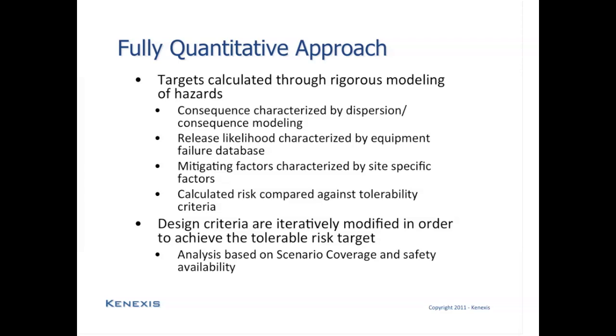The release likelihood is going to be calculated, but it's going to be calculated in a way that is drastically different than many people would expect, especially if they have a background in doing the simplified layer of protection analysis technique. With a fire and gas detection and suppression system, we do not assume that we are going to be able to know what the causes of loss of containment are. In fact, if a cause of loss of containment is well known and well understood, we would have expected that the process hazards analysis and the LOPA techniques would have adequately addressed the risks of those hazards using preventive techniques. Mitigative techniques, on the other hand, are to control those risks that are not well defined, not well understood, and cannot be well planned for ahead of time.